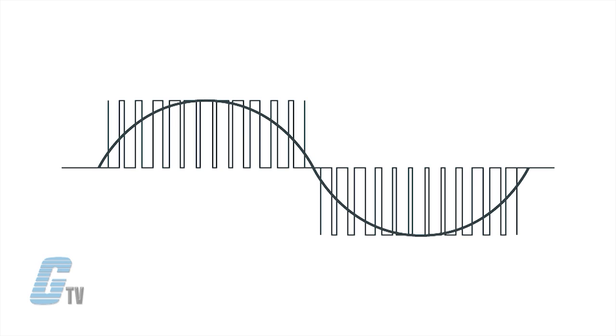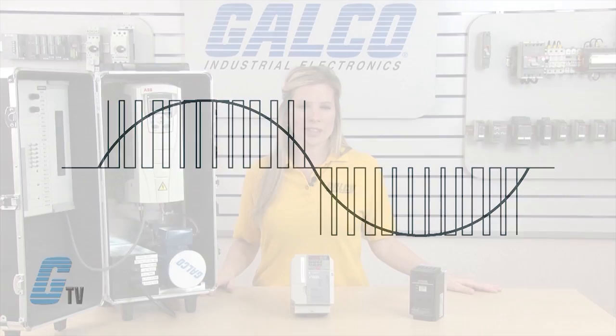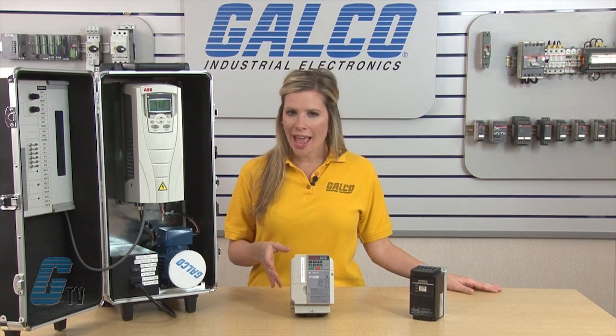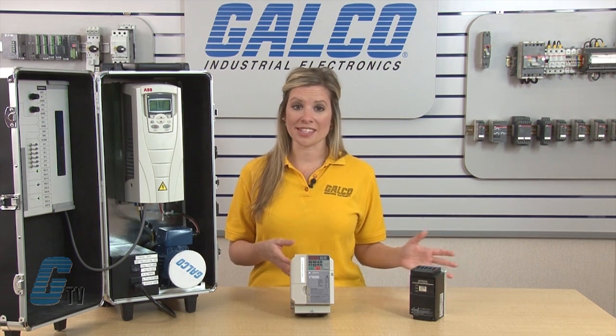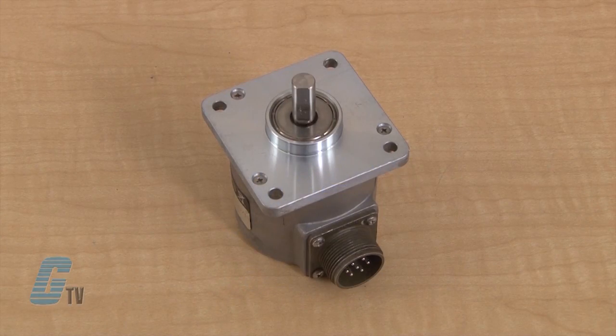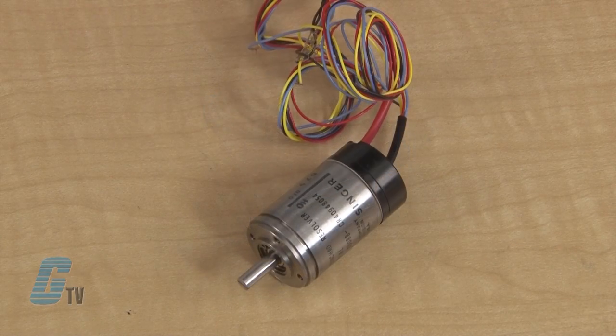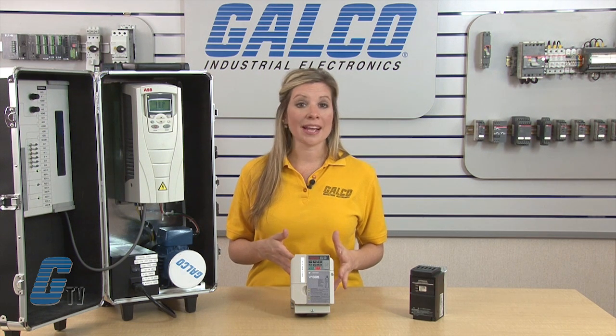The AC motor interprets this as an AC sinusoidal current waveform and moves as if it were such. By increasing or decreasing the pulse width through the drive, the AC motor responds. This particular system is an open loop vector system, and many VFDs are compatible with feedback devices such as encoders, hall effect pickups, and resolvers. The addition of any of these devices makes up a closed loop system.